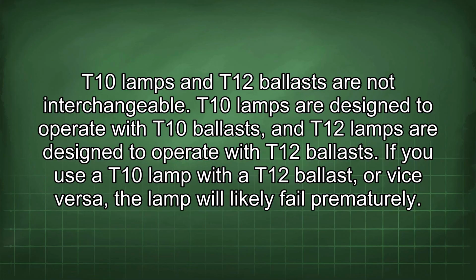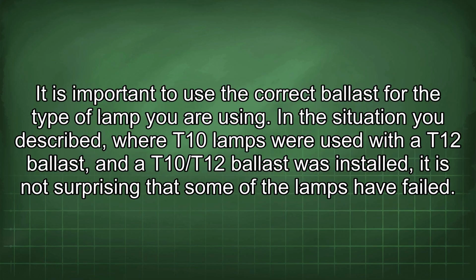T10 lamps and T12 ballasts are not interchangeable. T10 lamps are designed to operate with T10 ballasts, and T12 lamps are designed to operate with T12 ballasts. If you use a T10 lamp with a T12 ballast, or vice versa, the lamp will likely fail prematurely. It is important to use the correct ballast for the type of lamp you are using.